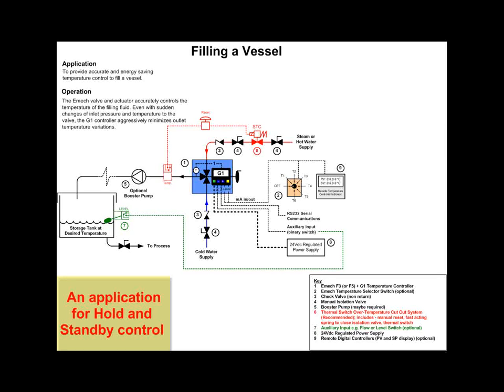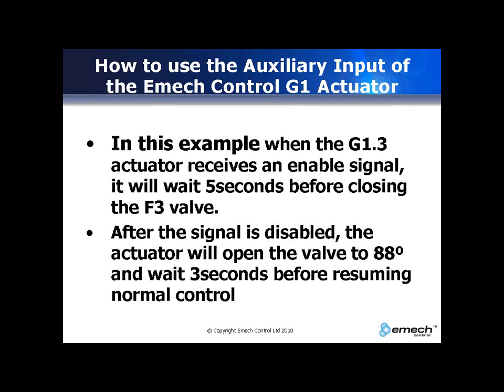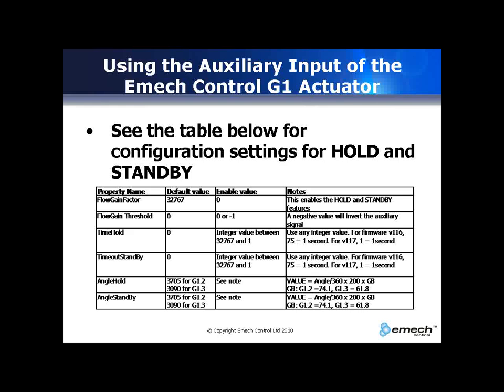When the level switch is triggered low, the auxiliary signal can start up the actuator and valve again, and this will begin to fill the tank. In this example, when the actuator receives an enable signal, it will stay in position for 5 seconds, and when 5 seconds has expired, it will move to 0 degrees, which is completely closing the valve. The actuator will stay in position until the signal is disabled. When this occurs, the actuator will open up the valve to 88 degrees, and after 3 seconds the actuator will resume normal control.